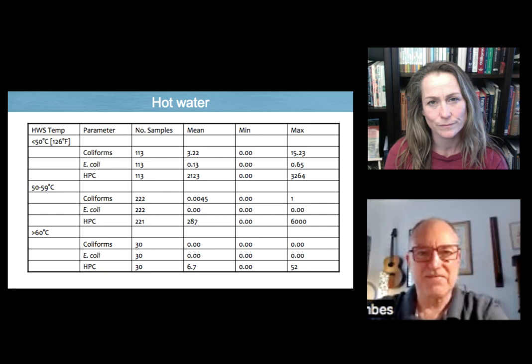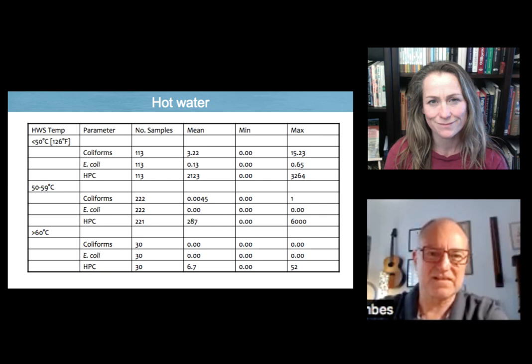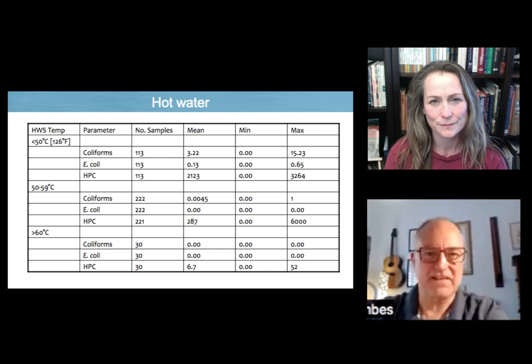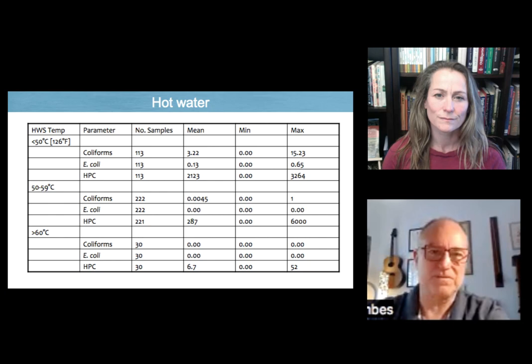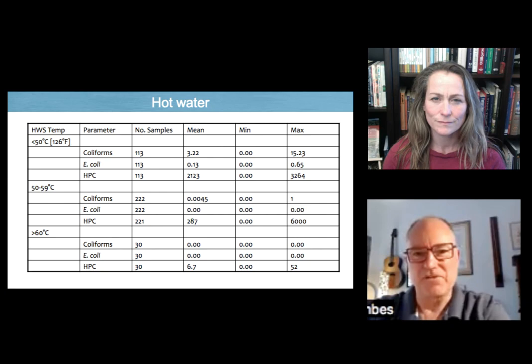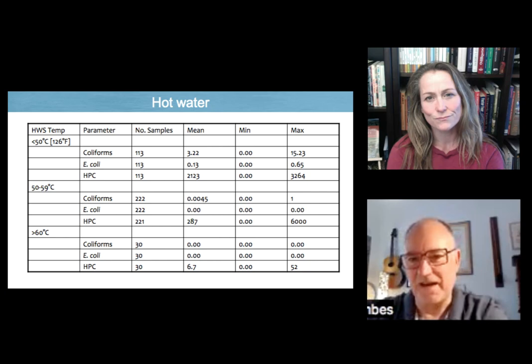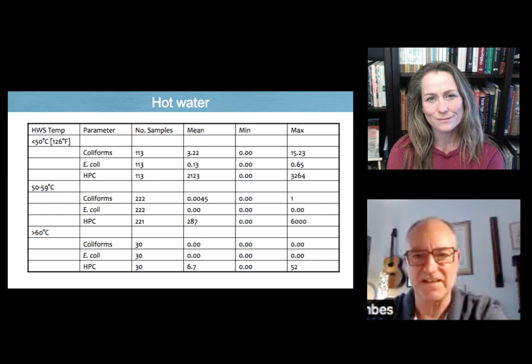What we actually found is that temperatures below 50 degrees Celsius, which is, I think, Michelle, you've kindly put 126 degrees Fahrenheit there, there was a very significant reduction in coliforms, E. coli, and heterotrophic plate counts, which is almost all bacteria. But there was some residual in the maximum column in the far right as you're looking at the screen. But the mean results, you can see very low counts.